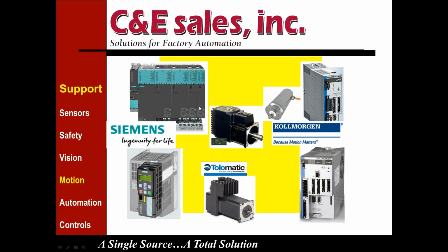Additionally, the modules on the right are double motor modules. So in 50 millimeter wide space, you can support two servo motors up to 9 amp continuous. So in these first two modules, that's four servos supported in only 100 millimeters. Next module over, we can go up to 18 amp continuous in a double motor module. So at a glance, you're looking at eight servo motors controlled in a very slim, compact package.